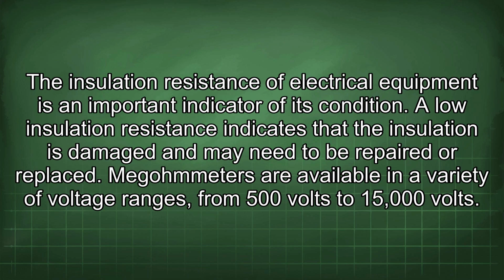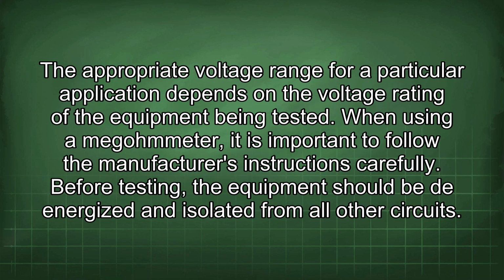The insulation resistance of electrical equipment is an important indicator of its condition. A low insulation resistance indicates that the insulation is damaged and may need to be repaired or replaced. Megohmmeters are available in a variety of voltage ranges from 500 volts to 15,000 volts. The appropriate voltage range for a particular application depends on the voltage rating of the equipment being tested.